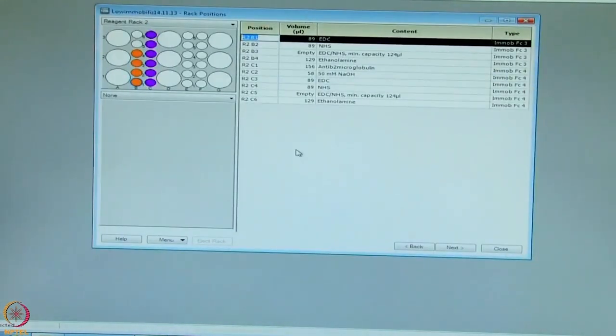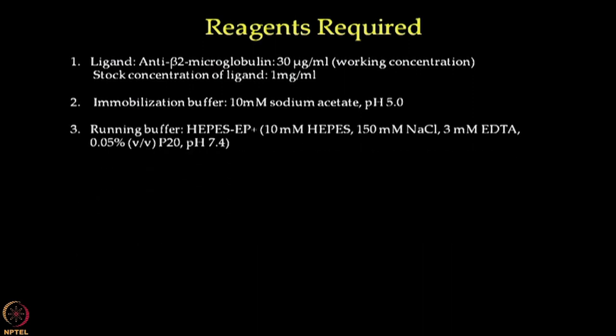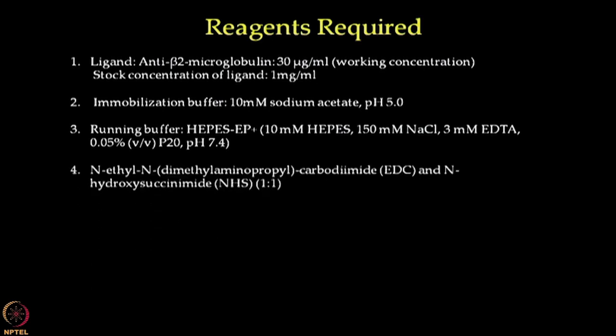Now we will add vials with rack positions and volumes. As per the volumes listed in the table, we will prepare the reagents for immobilization in a similar manner as demonstrated earlier in lecture 33. We prepared a working concentration of 30 micrograms per ml of beta-2 microglobulin antibody from a stock concentration of 1 mg per ml using an immobilization buffer of 10 millimolar sodium acetate pH 5.